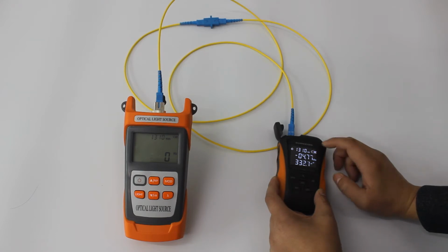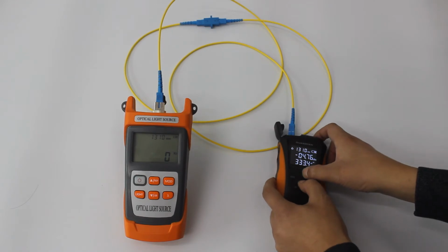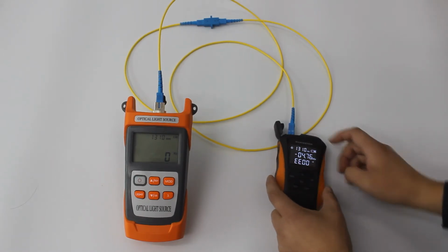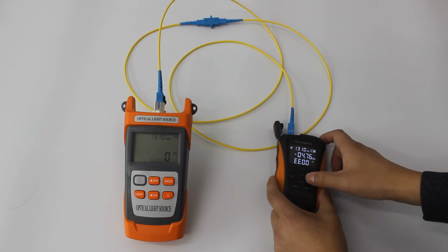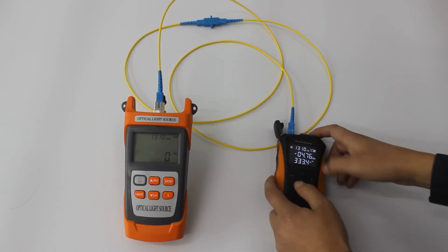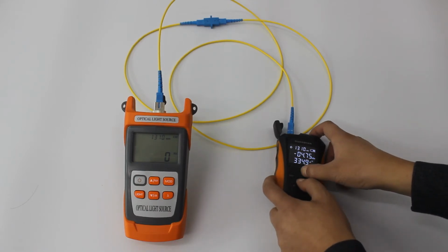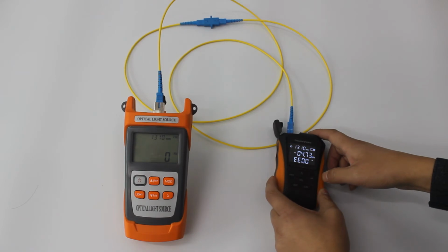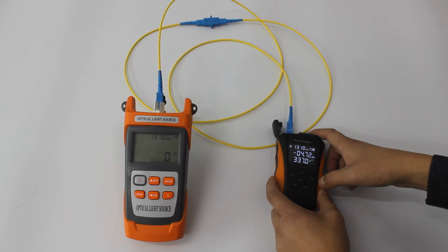Nanometer appears. Long press wavelength button and the dB button to enter the deletion mode. There are two options. Option 1, long press wavelength button and the dB button to exit from the deletion mode. Option 2, press dB button to delete all the data.